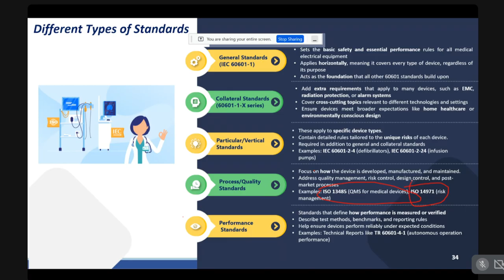In addition to that, there are standards called particular standards, which are specific to a medical device. If it is an infusion pump, then 60601-2-24 is applicable as a vertical standard or a particular standard. Likewise, depending upon the nature of the electromedical device, there are specific electrical standards that could apply. That is called product specific standards. In addition, we have process or quality standards. For instance, ISO 13485 is called a process standard. Then ISO 14971 is also called a process standard, because these standards focus on how medical devices are developed, manufactured, and maintained.